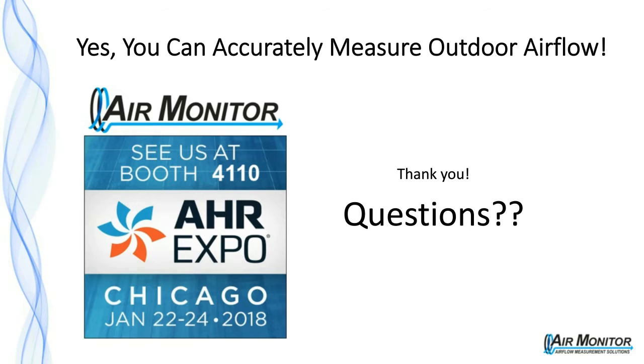Matt, you want to? Okay, the next question is, how often does a thermal dispersion flow station require cleaning or maintenance? For our system, it's really going to be application dependent. How much particulate contamination, how much moisture, how much buildup do you have on the sensors? I can say that thermal dispersion flow measurement devices are extremely sensitive to any contamination at all. So if there is relatively high dust loading, or there's particulate or moisture in there, they're going to have to be cleaned very often in an outside air application.